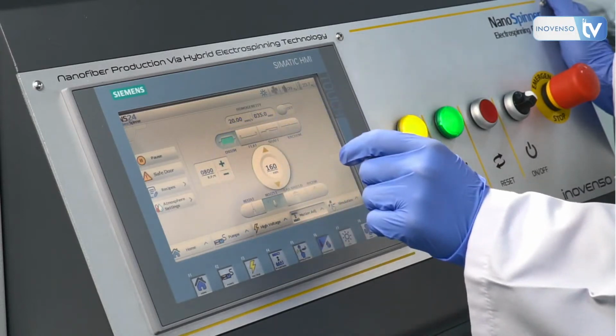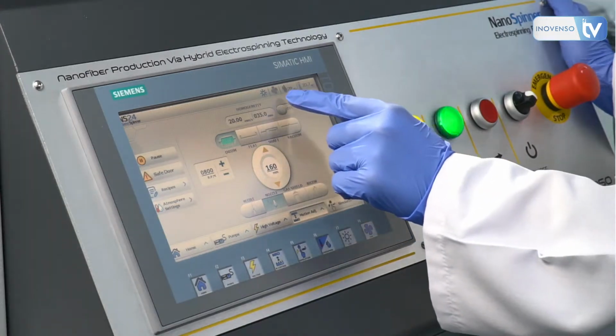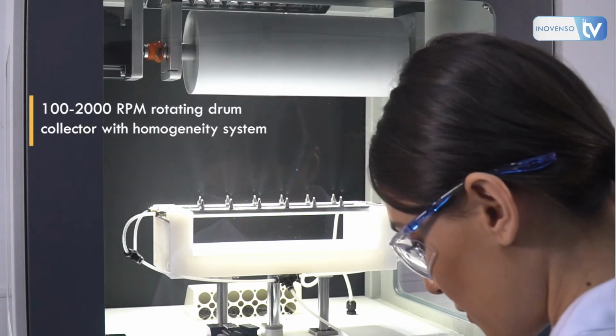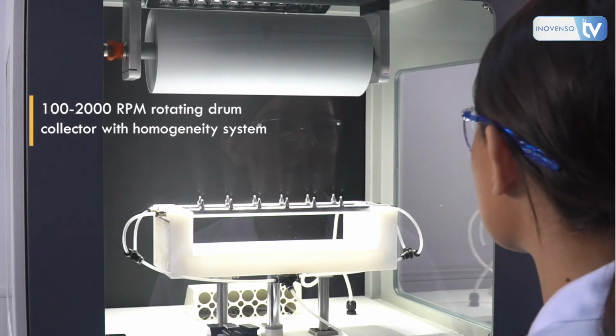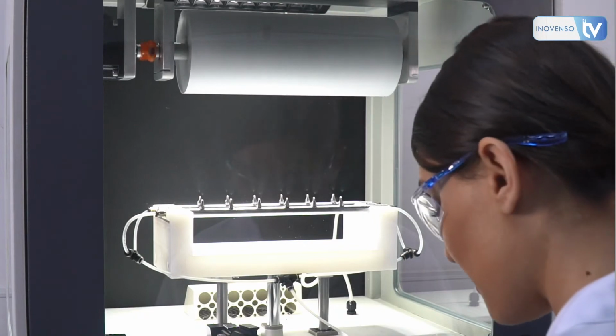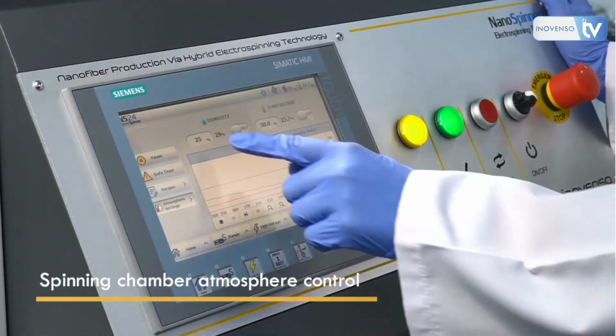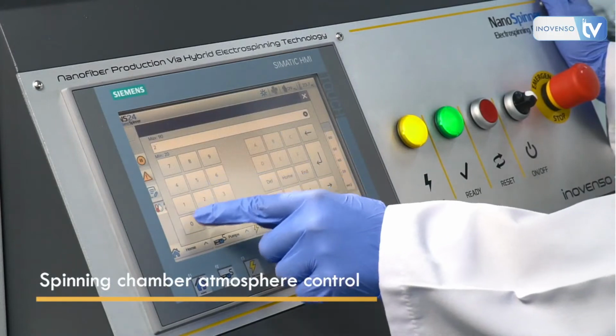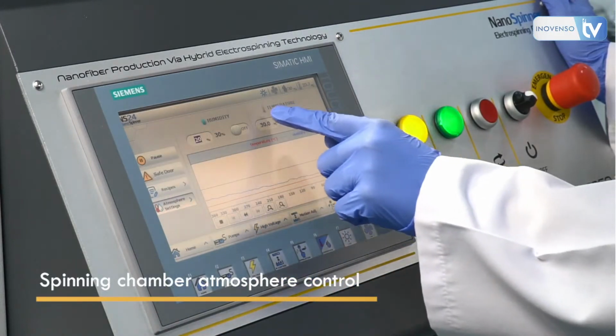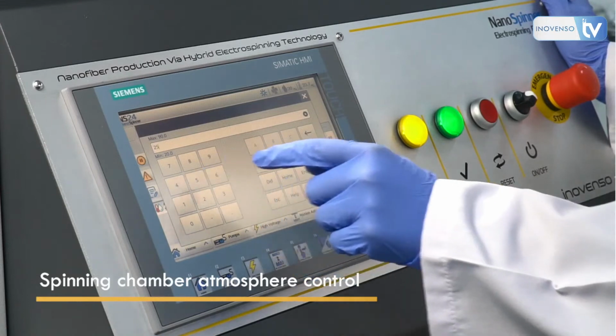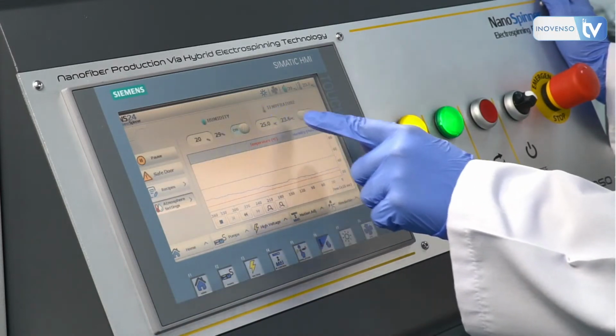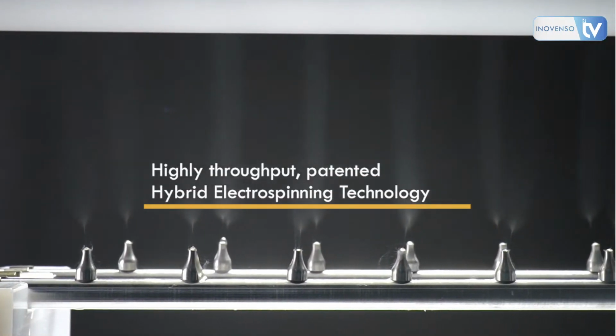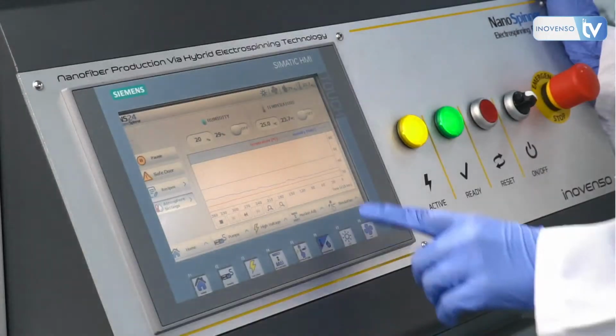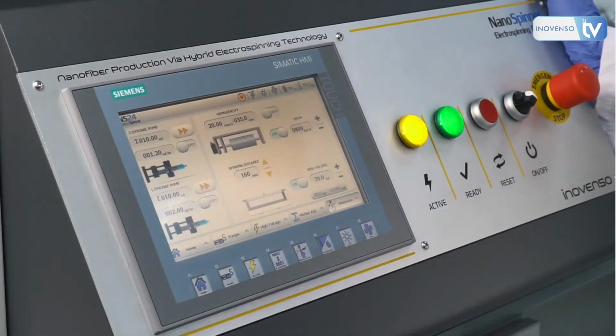So you can see on the screen there are actually 4 different collectors. That's the drum, that's the flat, and the shaft, of course. But right now for this demonstration, you have the drum. You also see that there's a uniaxial motion for the drum. It's for homogeneity, so that the nanofibers deposit evenly. And also for more advanced setups, if you have certain polymers that only electrospin well at a specific temperature or relative humidity percentage, you can control that accordingly with the machine.